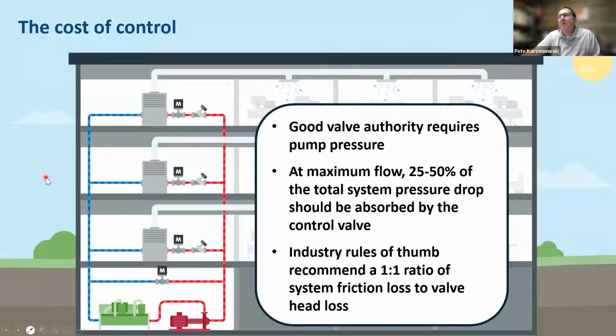And that control is expressed in valve authority. If we have a good valve authority in our system and the ability to control those pressure fluctuations and deliver the flow we need, we need to have pump pressure. At maximum flow, we talked about that design point, that maximum flow rate for our system, we need 25 to 50% of the total system pressure drop to be absorbed by the control valve. So up to 50% of the total system pressure drop being absorbed by the control valve.